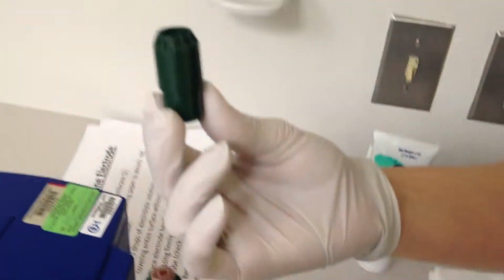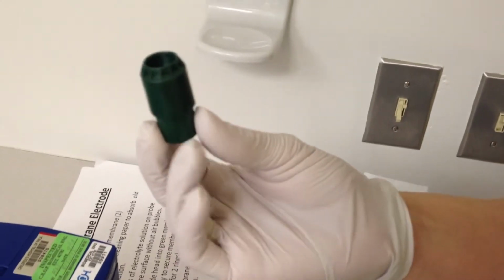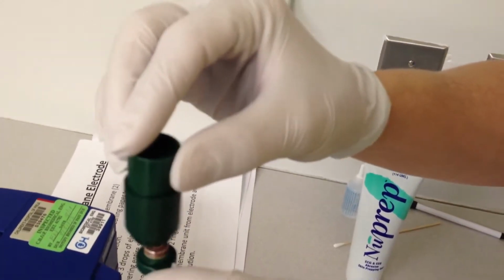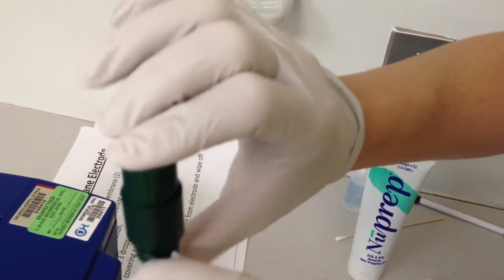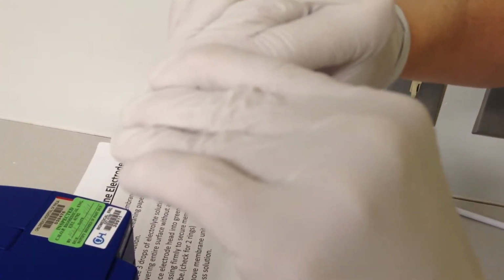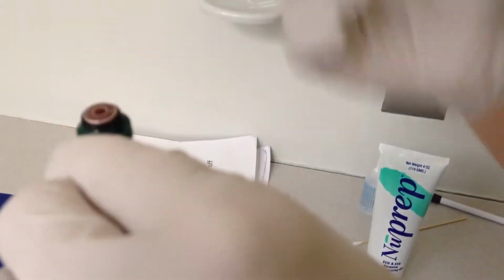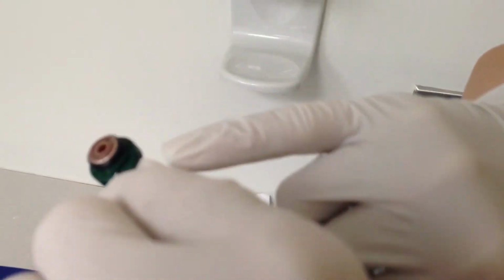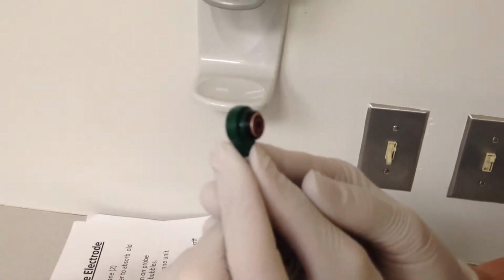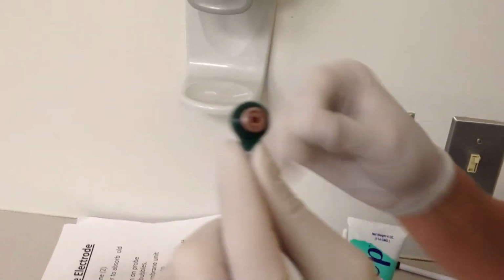Okay. Then you want to have your electrode and place it on top of the probe and a good push and hold. Then remove. After you remove, you want to make sure that you see the 2 rings to make sure you have a good seal. And then you want to look at the top of the probe and make sure there's no air bubbles. And I think we're good.